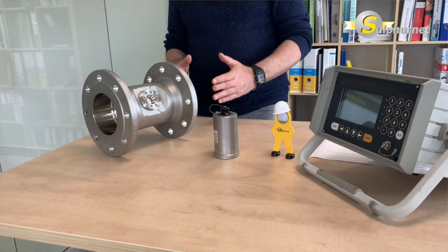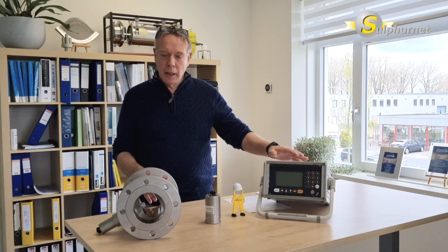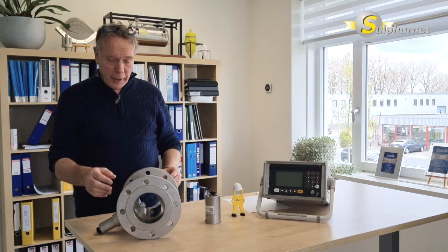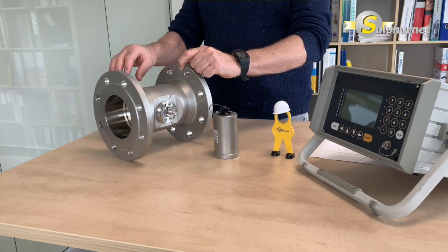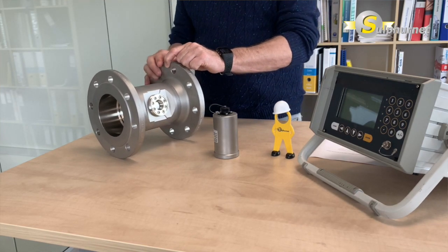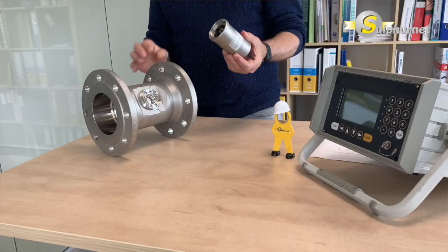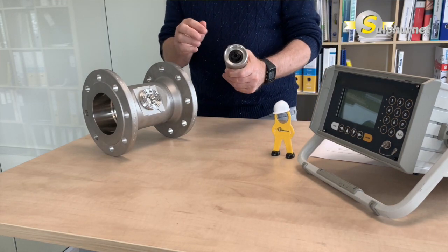We have two parts. One is the electronic device to measure the data, and one is actually the measuring cell. We have a path length, the liquid flows into the pipeline, and on one side we have a light shining through the sulfur with a certain path length, and on the other side we have a detector. The detector consists of multiple eyes, electronic eyes. There is a center eye.